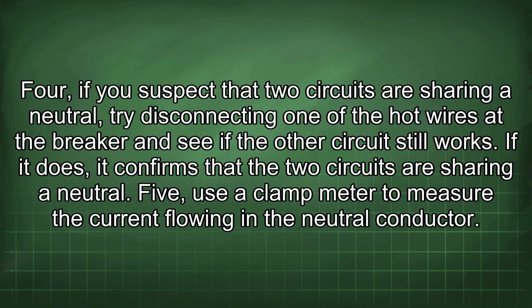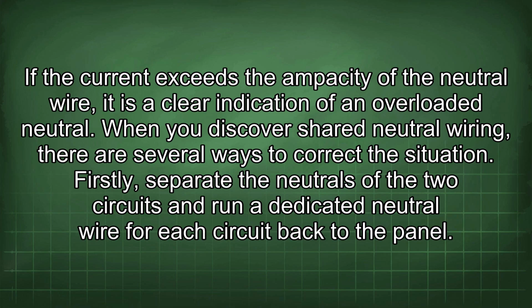4. If you suspect that two circuits are sharing a neutral, try disconnecting one of the hot wires at the breaker and see if the other circuit still works. If it does, it confirms that the two circuits are sharing a neutral. 5. Use a clamp meter to measure the current flowing in the neutral conductor. If the current exceeds the ampacity of the neutral wire, it is a clear indication of an overloaded neutral.